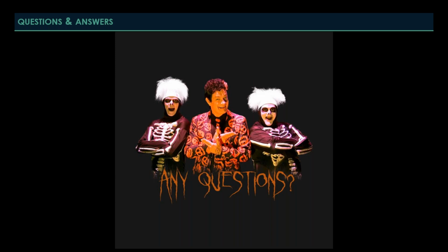There's a question about what is the energy efficiency achieved? So when we're designing radiant systems, if I'm looking at a radiant system in a high performance building and I'm comparing that to an ASHRAE baseline, my target is typically going to be 30 to 50% better than an ASHRAE baseline. So these are significant improvements that you can achieve with these types of systems.